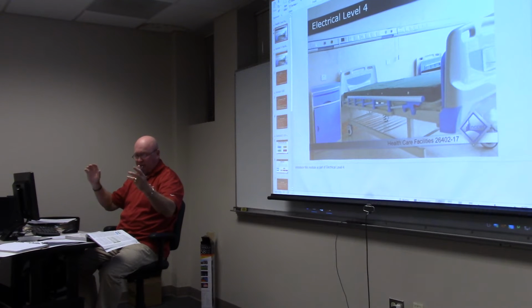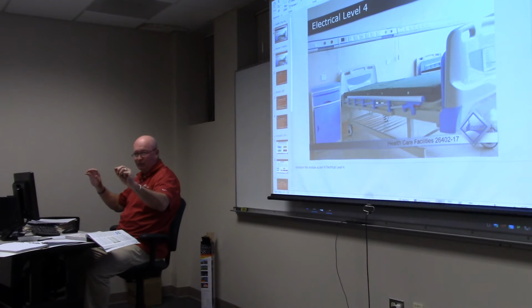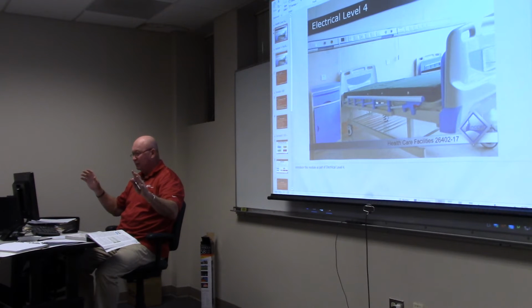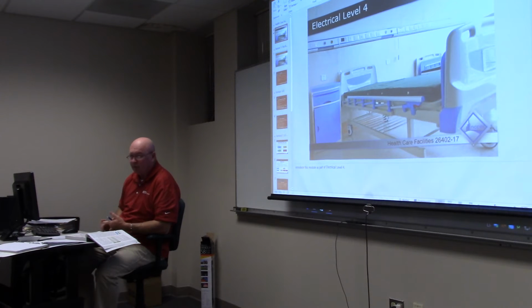And now notice that the equipment branch is what? It's kind of in yellow, isn't it? So yellow just means what? Be going through a red light. Slow down, it's not critical. But notice the other two are what? They're in red. So you think the red are more important? Those two areas? Sure they are. Critical branch, that word tells me that it's pretty important. And then life safety, that word definitely tells me that they're important. So they're more in the red, and we'll be discussing what the limitations are on that, okay?